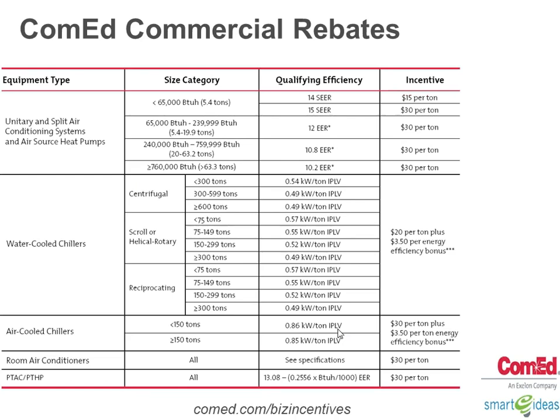Normally you're going to be at some kind of part load operating scenario, either because there's less people in the building or because it's cooler outside or whatever. So you look at the part load value, which is defined by AHRI. Let's say I have an air-cooled chiller, 100 tons, so I've got to be at least 0.86 kW per ton. If I hit that amount, I get $30 per ton. So for 100 tons, I would get a $3,000 rebate.